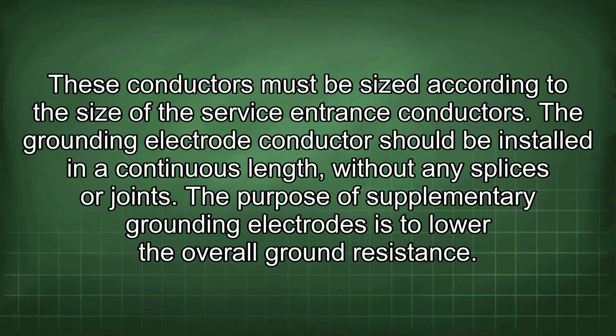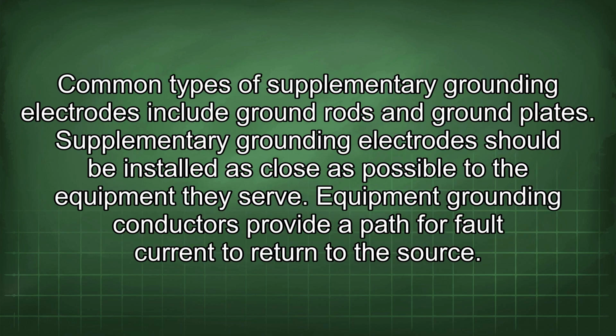The purpose of supplementary grounding electrodes is to lower the overall ground resistance. Common types of supplementary grounding electrodes include ground rods and ground plates. Supplementary grounding electrodes should be installed as close as possible to the equipment they serve.